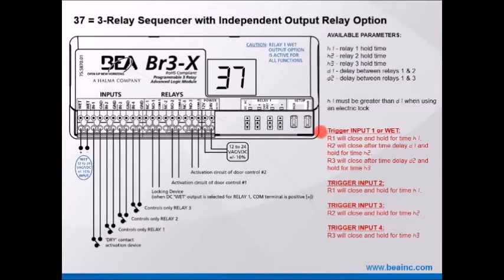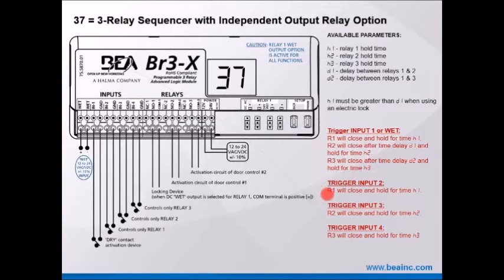Trigger input one or the wet input: relay one R1 will close and hold for H1. Relay two will close after delay D1 and hold for H2. R3 will close after D2 delay and hold for H3. If you trigger input two, only R1 will close and hold. Trigger input three, only R2 will close and hold. Trigger input four, only R3 will close and hold for its respective hold time.